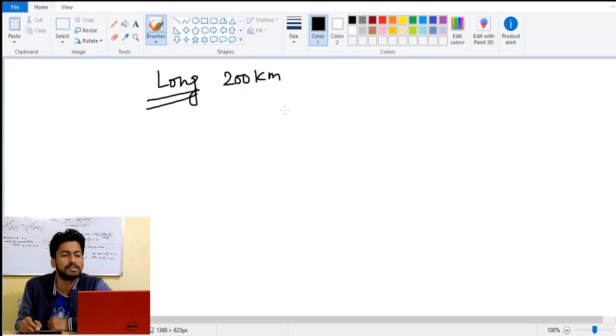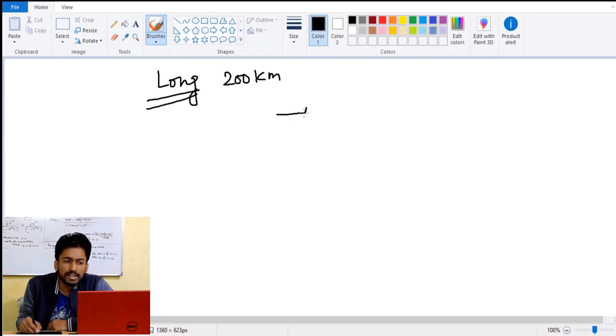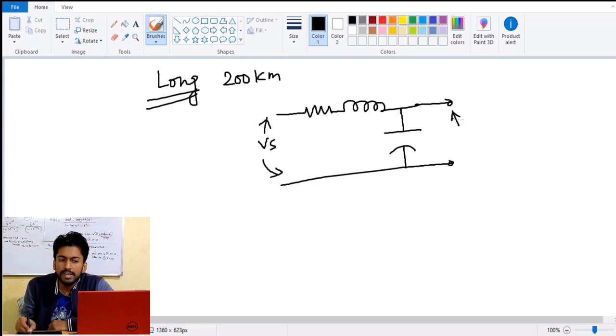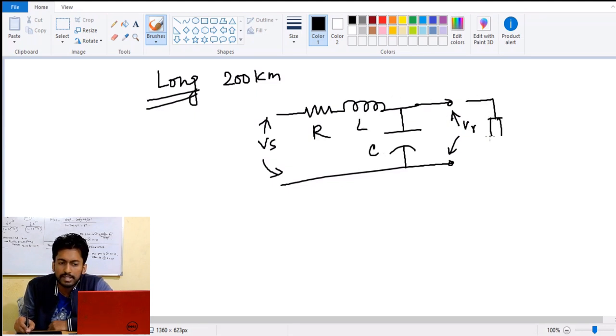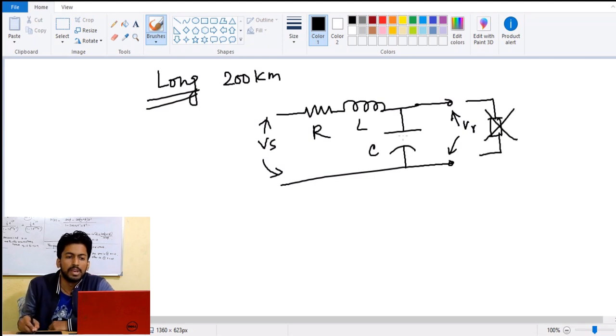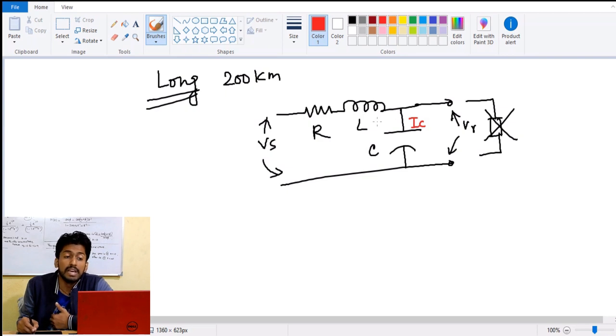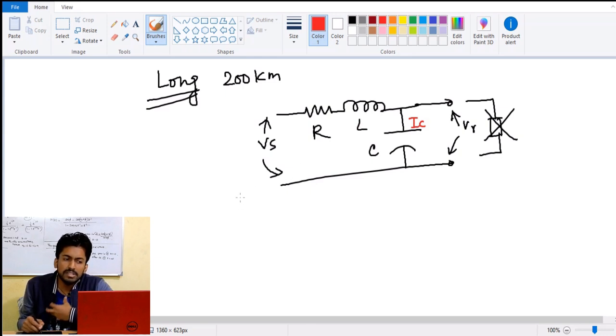If we consider a small section of the line, the resistance, inductance, and capacitive parts are present as line parameters. This is the sending end voltage and this is the receiving end voltage, but there is no load connected. The only thing flowing through this circuit is the charging current. This charging current will produce a voltage drop, and the inductive drop will be very less because the charging current exists due to the capacitive effect — capacitance is predominant.